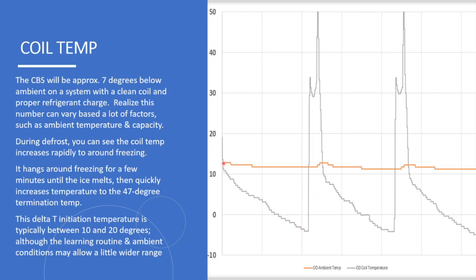So as you can see here, they start at the same temperature. Ambient remains relatively consistent. It does fluctuate during the defrost. But you can see the coil temperature slowly getting colder and colder and colder until such time as the system says, okay, we've become inefficient, it's time to defrost. So it goes into a defrost cycle. That coil temperature rises to 32 Fahrenheit roughly.